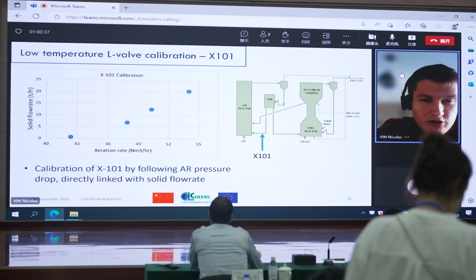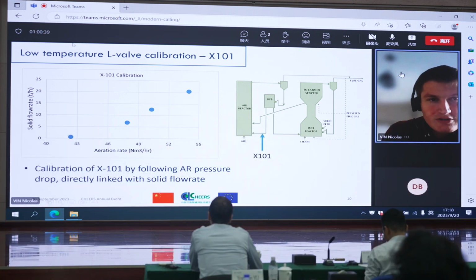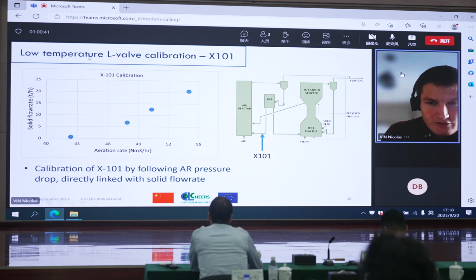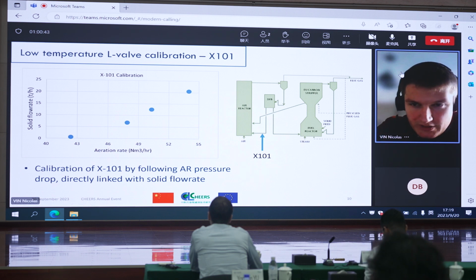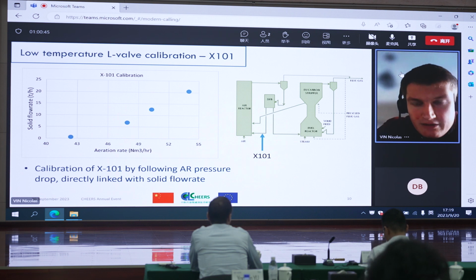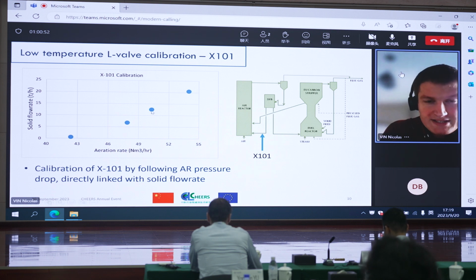Yeah, so for calibration, that's really at low temperature. The fluid circulation in the L valve really depends on the temperature and pressure balance. So it's quite sensitive - when you increase the temperature inside the valve a little, it increases the solid flow rate a lot.